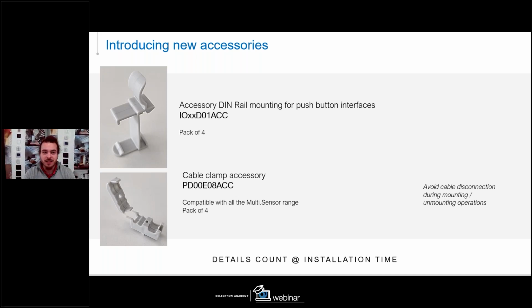In addition, we release a new cable clamp for the presence detector. This plastic accessory must be mounted on the back of the presence detector and is used to clamp the input wire that we have on the back of the presence detector itself. This could be very useful when you mount and dismount the product from the ceiling, avoiding the cable disconnection from the device itself. So this can be very useful for maintenance and also for the installation procedure.